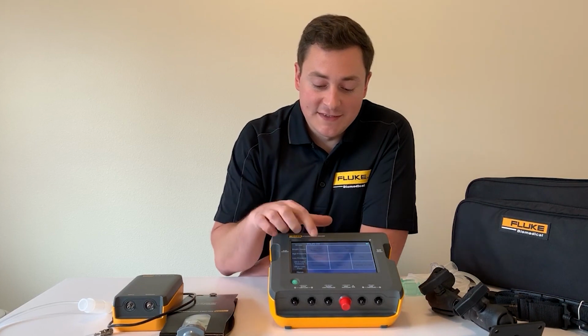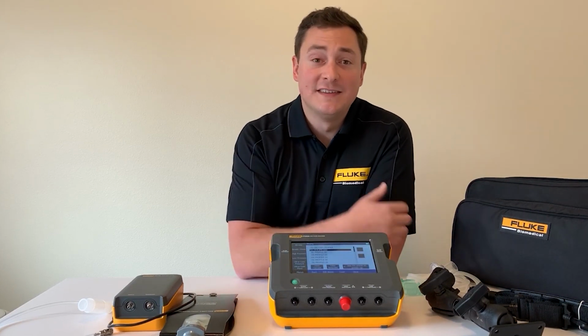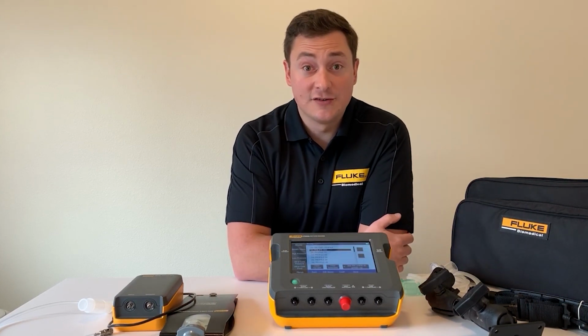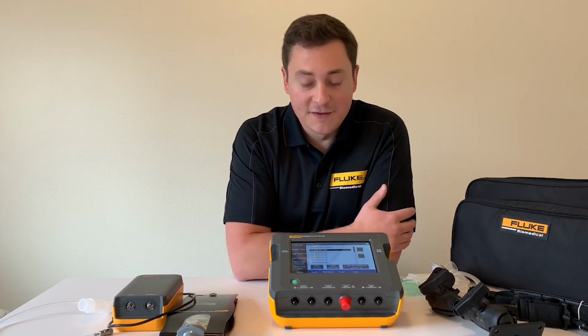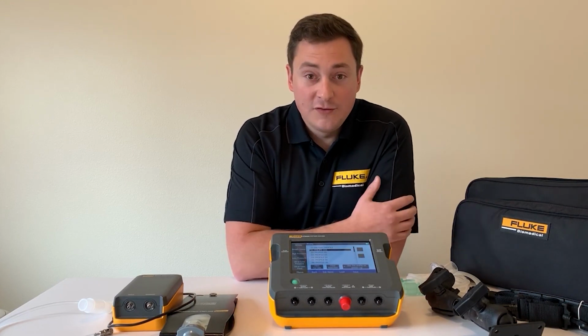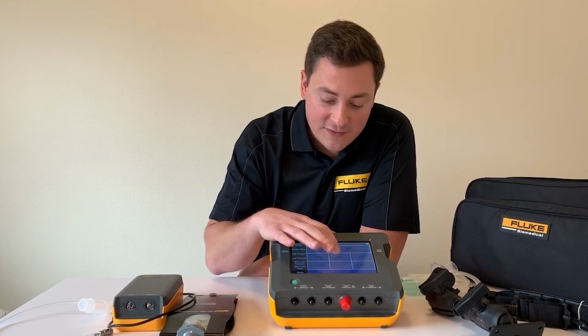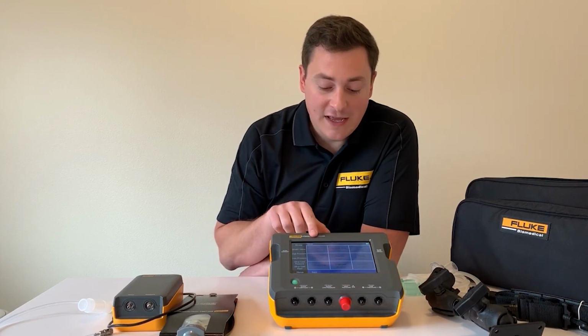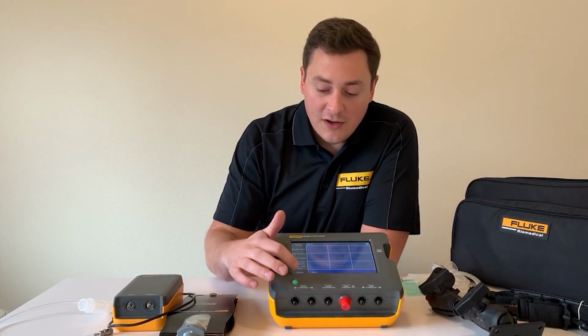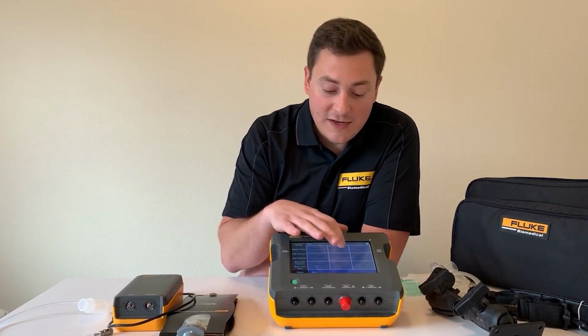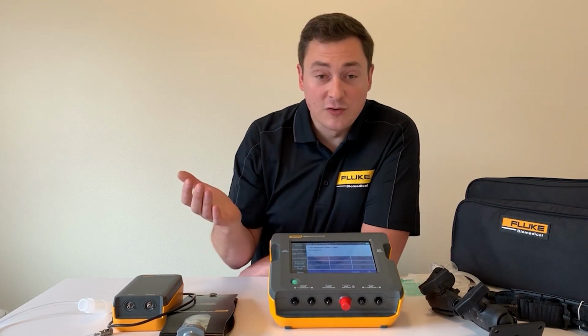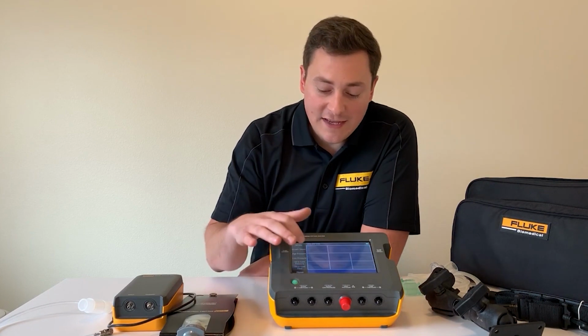The other thing that's nice is test profiles. A test profile is the brand and model of medical device that you're testing. In this case, I called it a Philips V60. What can you do to that? Well, if you go back to menus in setup, you can set up your gas type, your correction mode. You can go back and set up any units you want and change those very quickly, but you can save it all under a test profile.